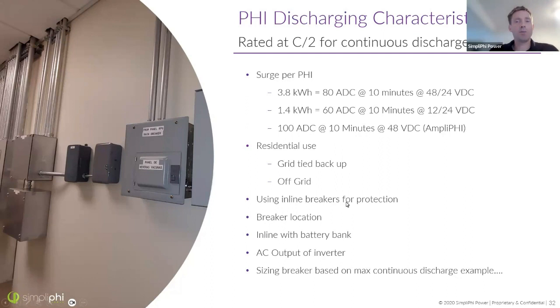Consider using inline breakers for protection. And be careful where you locate those breakers. Battery breakers: there needs to be a disconnect between your battery bank and your inverter, but all of our batteries have breakers built into them. They have 100 amp breakers built in, so that can act as a disconnect.